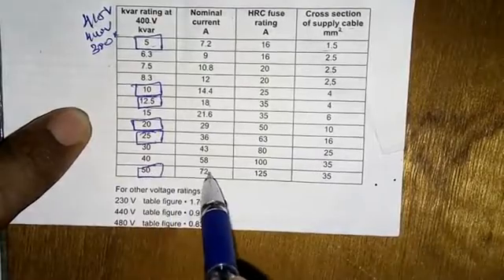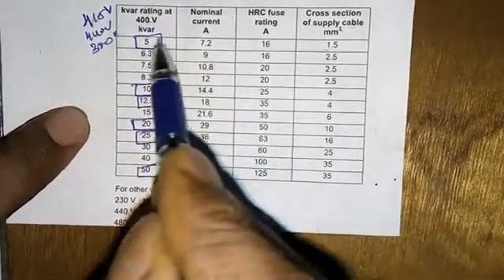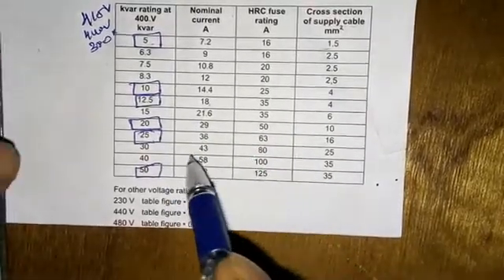For 25 kVAR, it's 36 ampere with 63 ampere fuse link and 16 square mm cable. For 50 kVAR, it's 72 ampere with 125 ampere fuse link and 35 square mm cable. This is the way you choose the cable or wire to connect to the capacitor bank for the load.